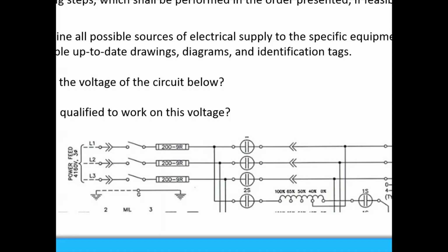I once saw a person who was going to change out a 3-phase 480 volt motor. He disconnected the motor, which was no issue. But there was another circuit in there, a heater circuit to keep the windings dry and prevent condensation. He didn't lock and tag that one out, didn't establish an electrically safe work condition on it, and unfortunately that cost that man his life.